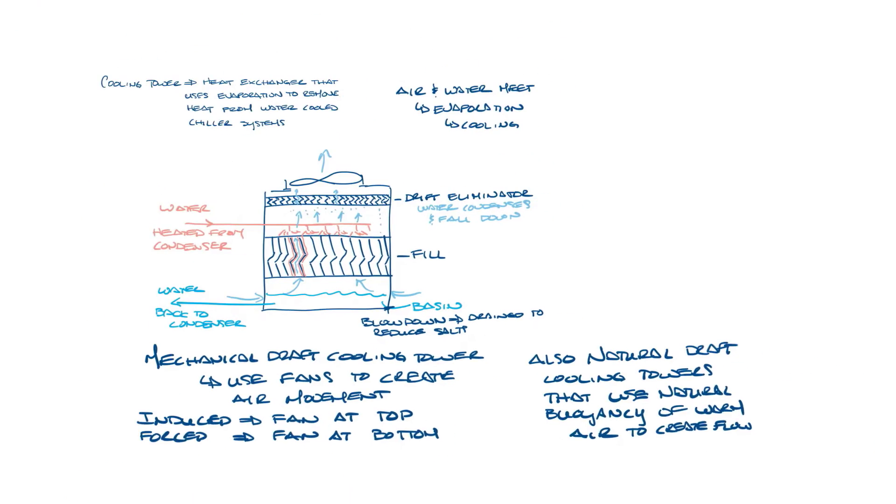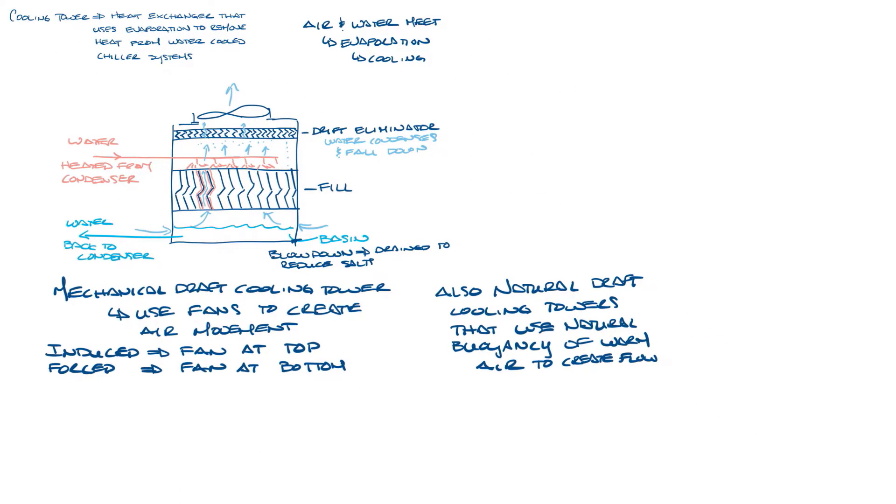Let me make more room again so I can talk about counter flow and cross flow towers. What I've drawn here is a counter flow tower. In counter flow towers the water spraying into the tower over the fill flows downward while the air moves upward.